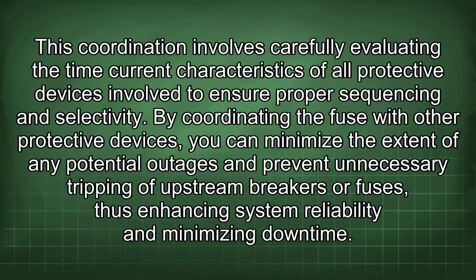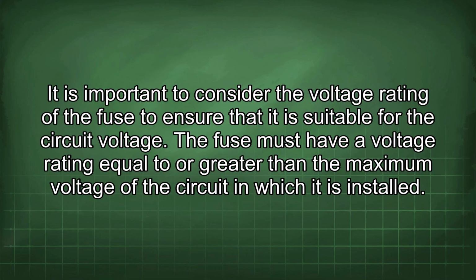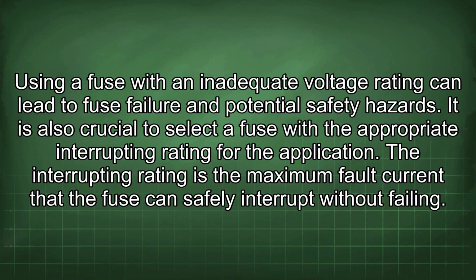This coordination involves carefully evaluating the time current characteristics of all protective devices involved to ensure proper sequencing and selectivity. By coordinating the fuse with other protective devices, you can minimize the extent of any potential outages and prevent unnecessary tripping of upstream breakers or fuses, thus enhancing system reliability and minimizing downtime. It is important to consider the voltage rating of the fuse to ensure that it is suitable for the circuit voltage. The fuse must have a voltage rating equal to or greater than the maximum voltage of the circuit in which it is installed.